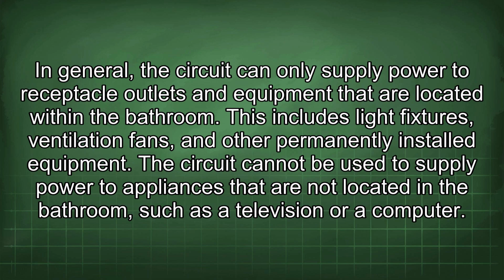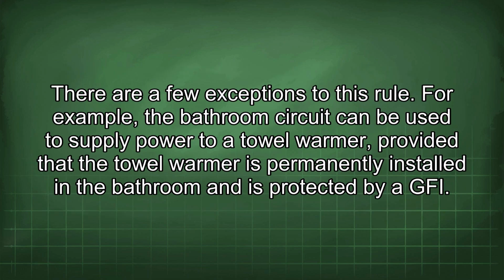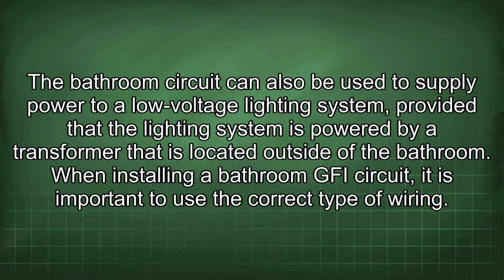The circuit cannot be used to supply power to appliances that are not located in the bathroom, such as a television or a computer. There are a few exceptions to this rule. For example, the bathroom circuit can be used to supply power to a towel warmer, provided that the towel warmer is permanently installed in the bathroom and is protected by a GFI. The bathroom circuit can also be used to supply power to a low-voltage lighting system, provided that the lighting system is powered by a transformer that is located outside of the bathroom.